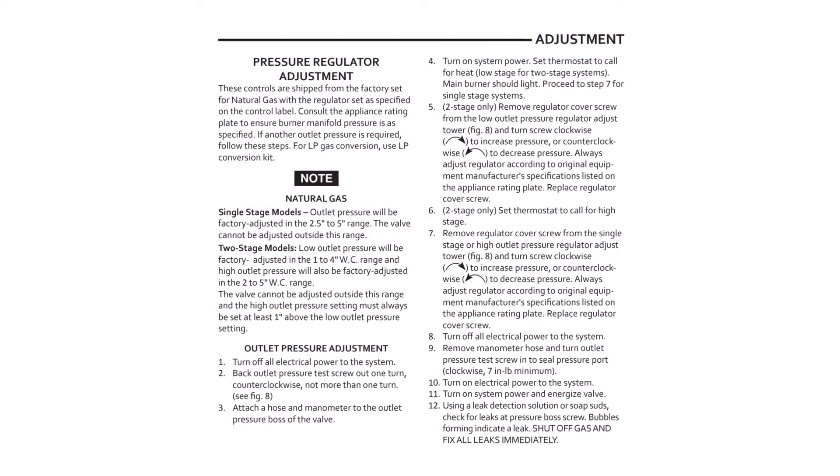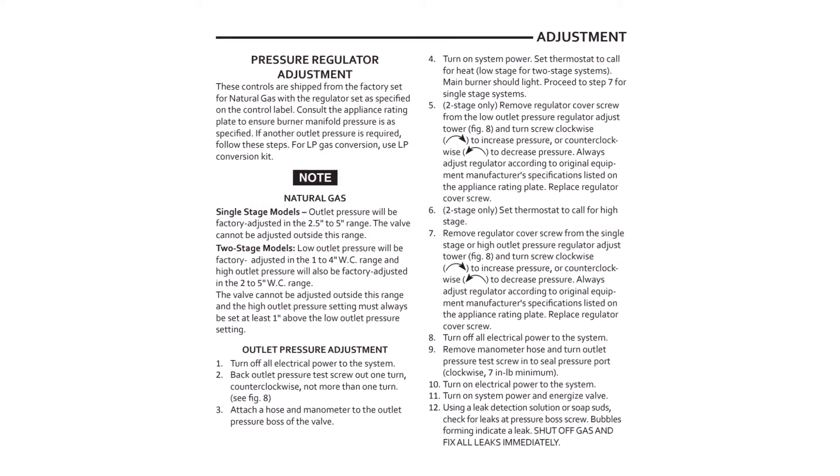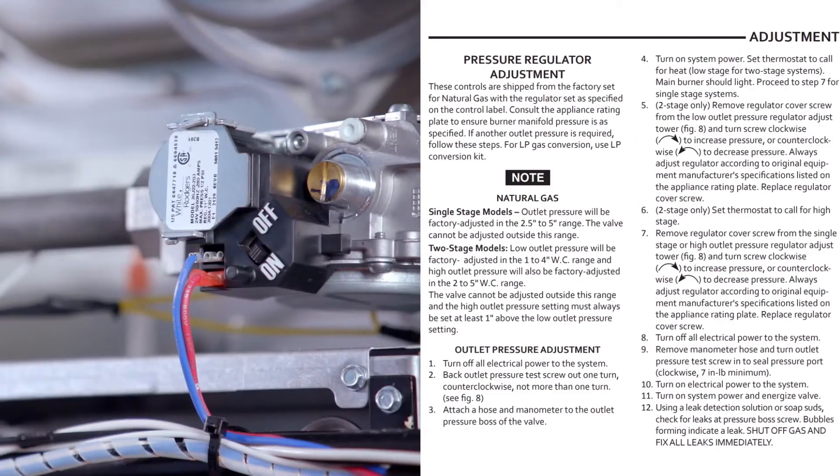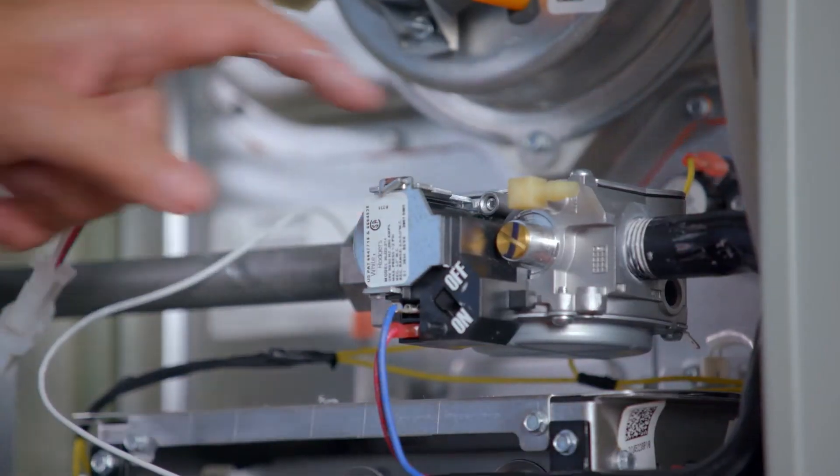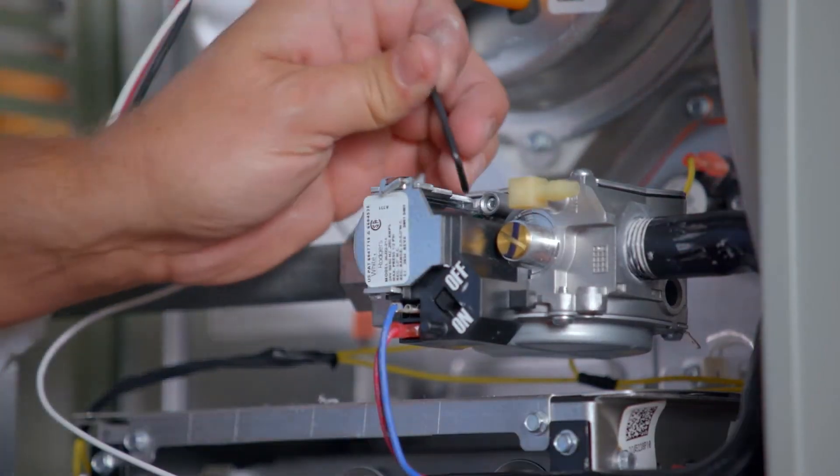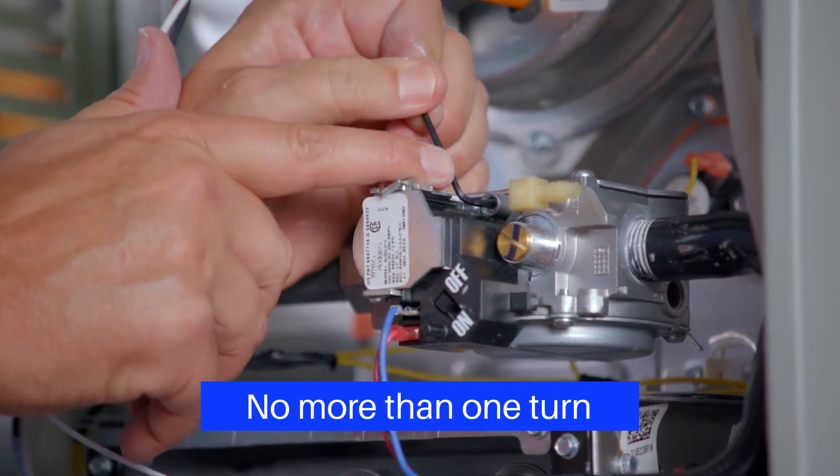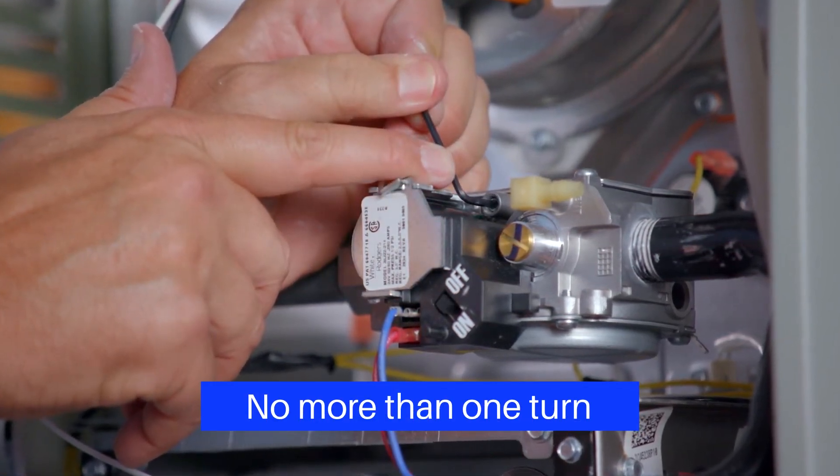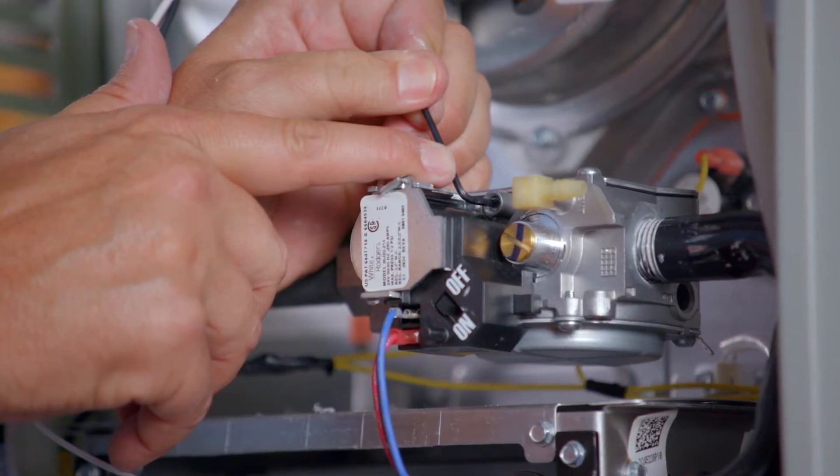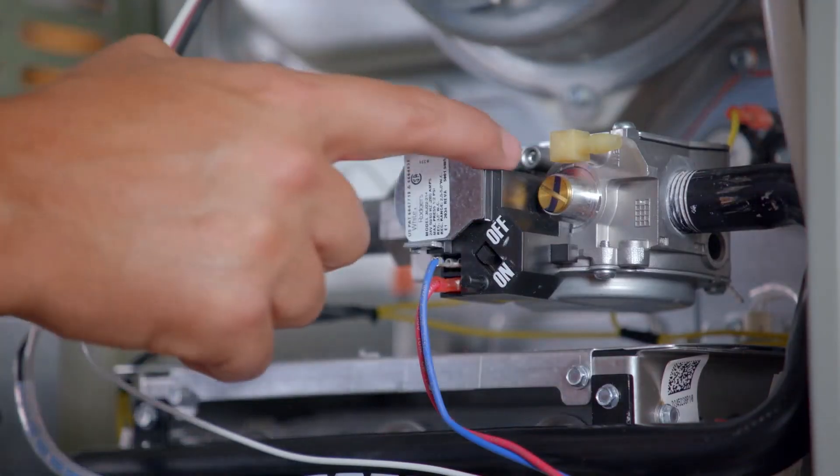The system is now ready to be tested. Following the instructions supplied with the gas valve, prepare the gas valve for gas pressure testing. With gas and electrical power still off, identify the outlet pressure post, sometimes called a tower, labeled OUT-P, and back the outlet pressure test screw out one-quarter to one-half a turn. The post accepts a 5/16th hose connection.